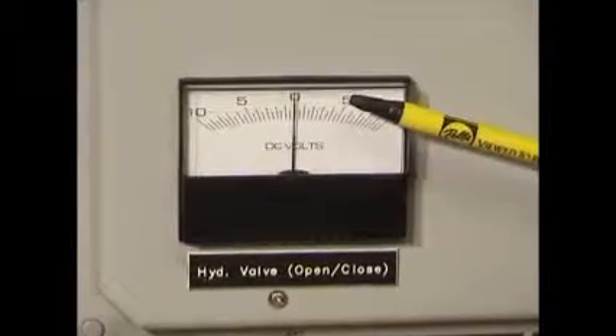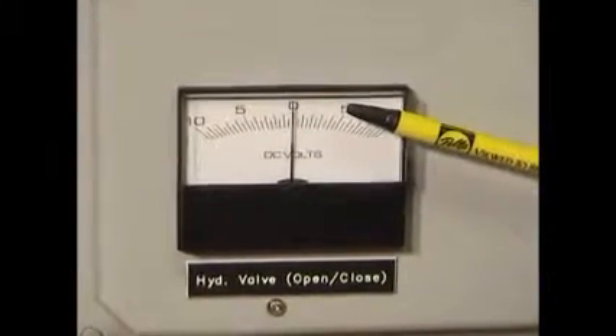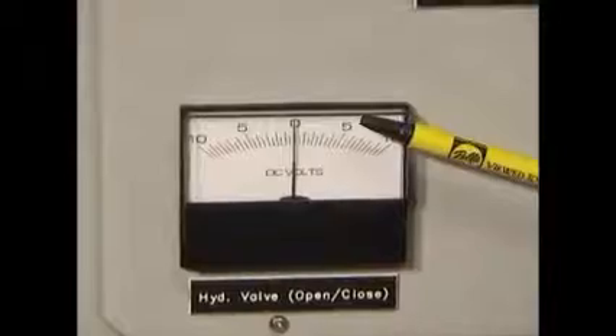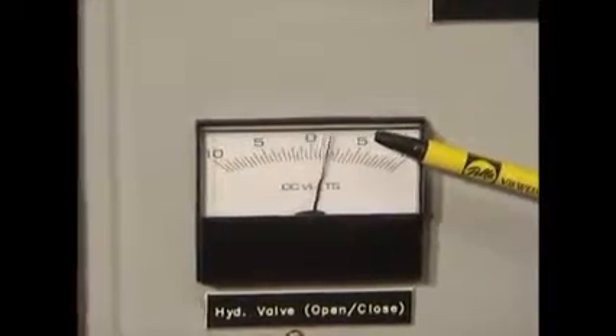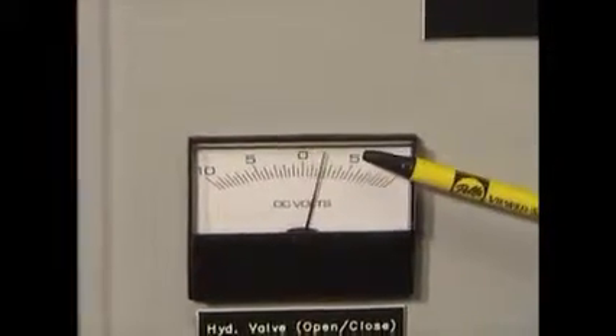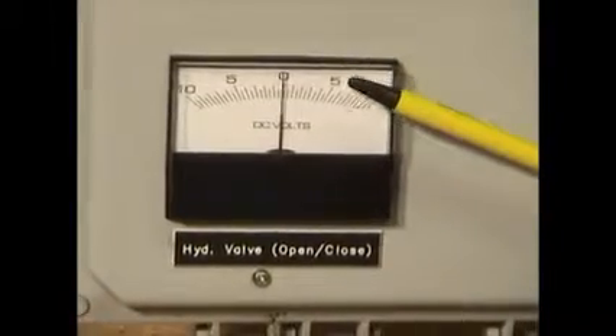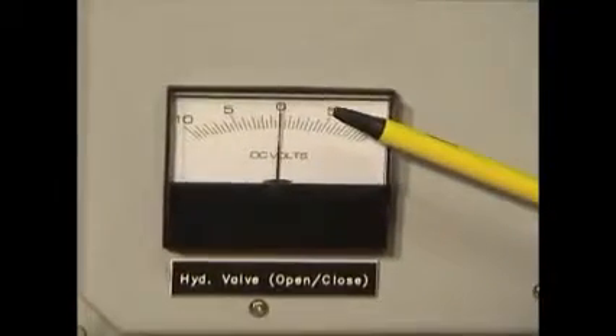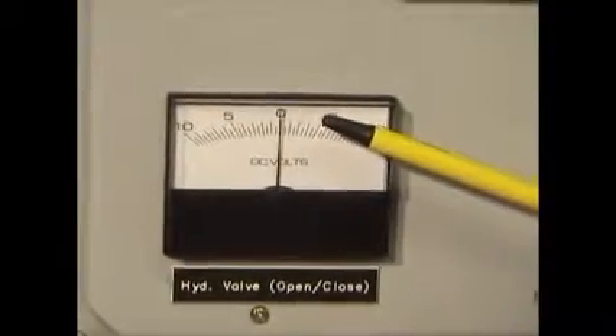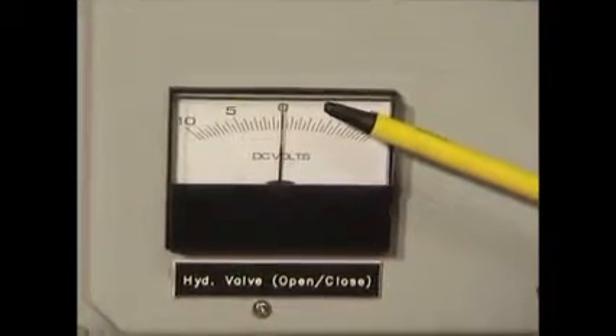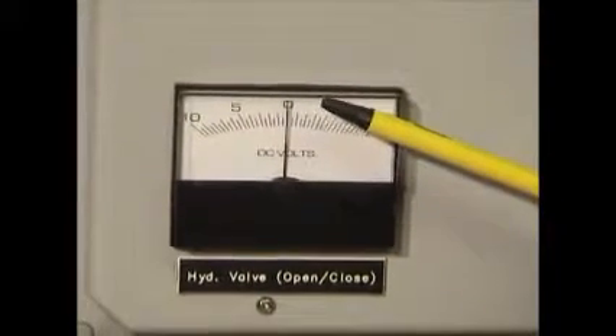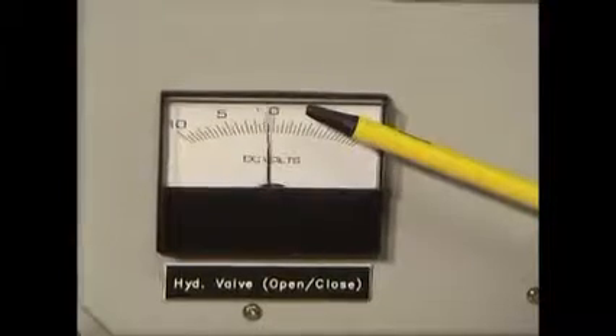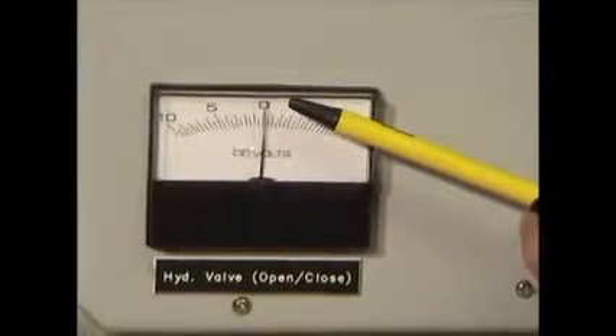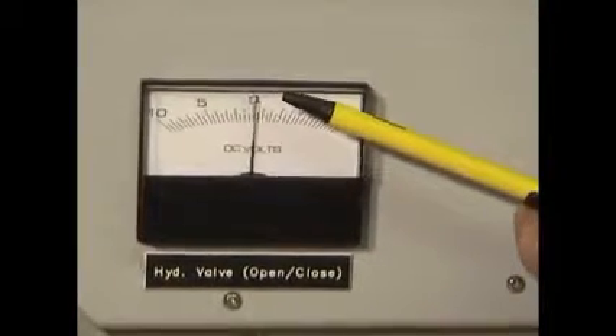When the valve is opening, you'll see the meter go to the right, or a positive voltage, each time the valve opens. When the valve is closing, the analog output module sends a negative voltage to the proportional valve, going in a negative direction to close the valve.